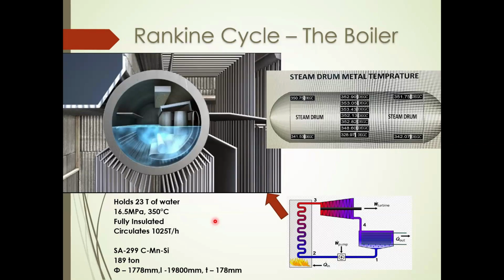But for the purpose of cooling down, this is where the problem comes. It takes about 4 to 5 days because of the thick structure of the steam drum. This is also because the temperature that we can achieve in the pumping phase is about 120 to 150 degrees Celsius unless the boiler is being fired. When firing is not available in the boiler, the pumping temperature that we can achieve is about 130 degrees Celsius from the use of the auxiliary boiler.